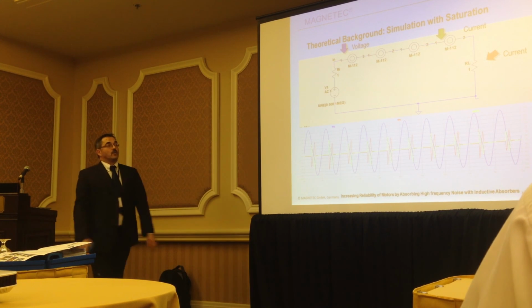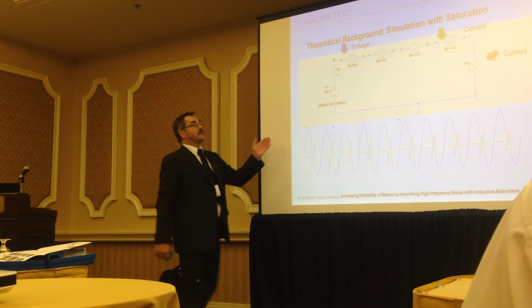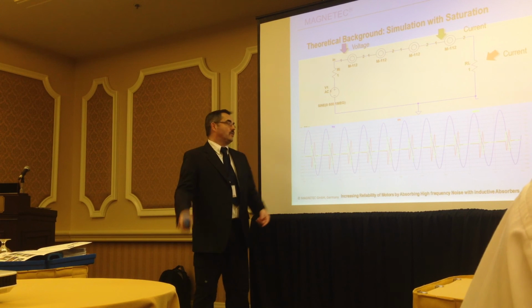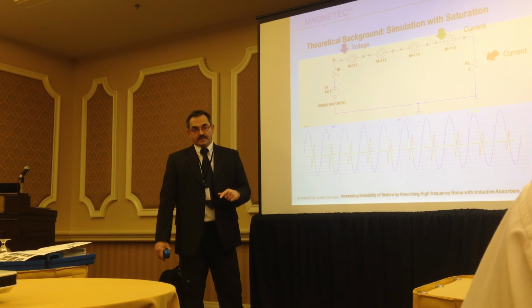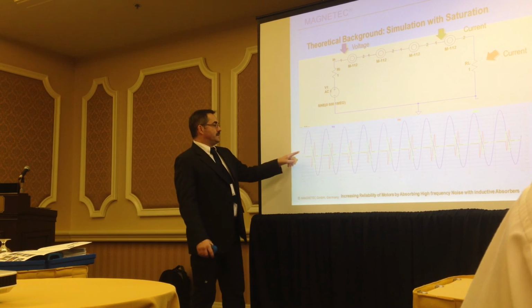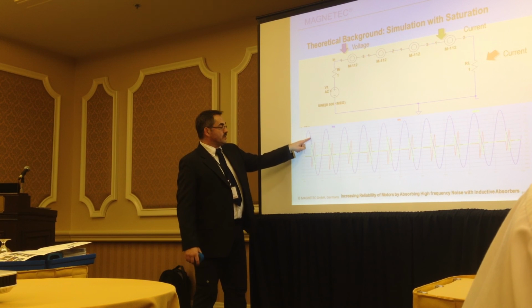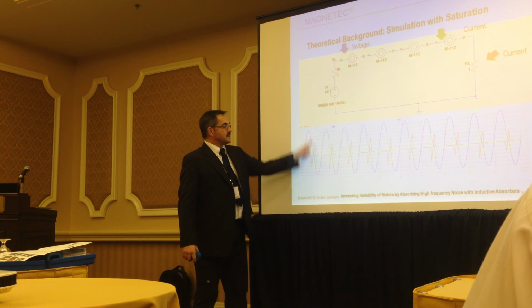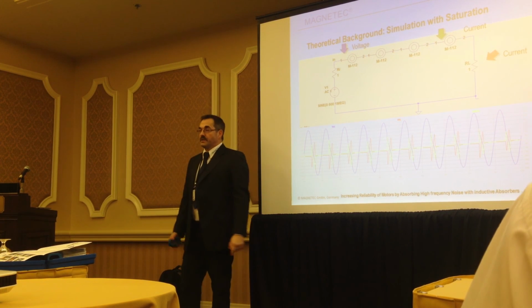That means a core, if the common mode current is too big - which can happen on very long motor cables or bad grounding situations, that's another point - can only handle a certain voltage-time section, and then the current starts to peak up again. The good thing is...